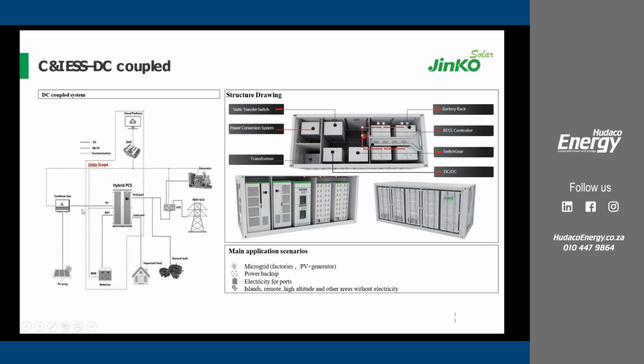So you can see in this scenario, in as much as we supply, for example, the small 50 kilowatt hybrid PCS, it usually has the PCS and also the DC-DC. I will still show you a picture of how it looks. But of course, if it's a 50 kilowatt system, then that means one input for the PV. For you to have one input for the PV, you need to combine multiple PV strings, let's say 5 to 8 strings, so that you can connect to the DC-DC unit. This is not usually supplied as part of the accessories, so I'm just letting you know.